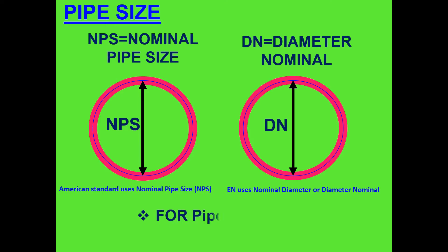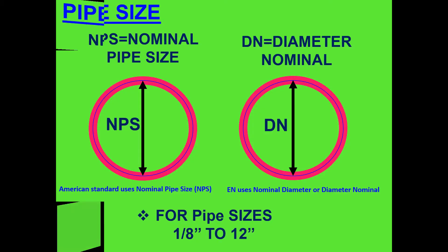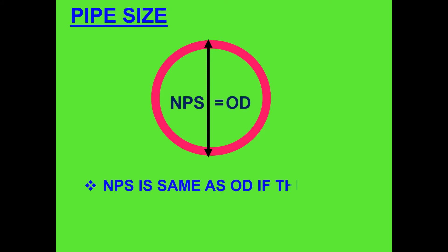Important point to take note: here you can see some difference in nominal pipe size. NPS is the same as OD, which means nominal pipe size is the same as outer diameter, if the pipe size is from 14 inches and above.